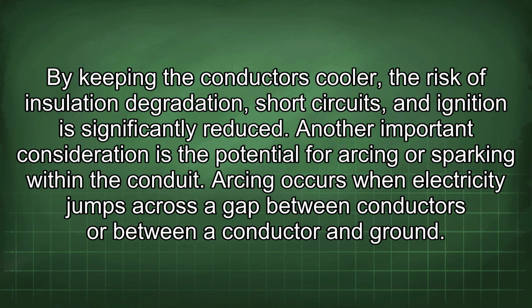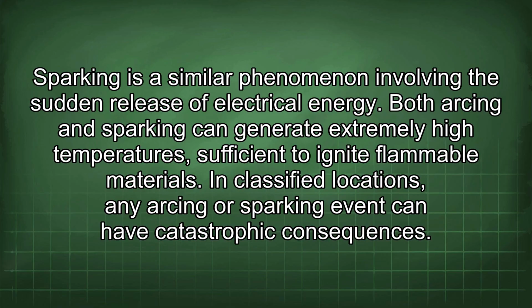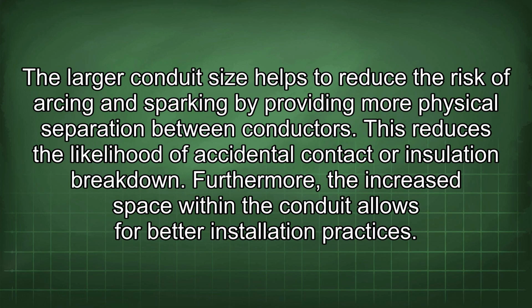Another important consideration is the potential for arcing or sparking within the conduit. Arcing occurs when electricity jumps across a gap between conductors or between a conductor and ground. Sparking is a similar phenomenon involving the sudden release of electrical energy. Both arcing and sparking can generate extremely high temperatures, sufficient to ignite flammable materials. In classified locations, any arcing or sparking event can have catastrophic consequences. The larger conduit size helps to reduce the risk of arcing and sparking by providing more physical separation between conductors. This reduces the likelihood of accidental contact or insulation breakdown.